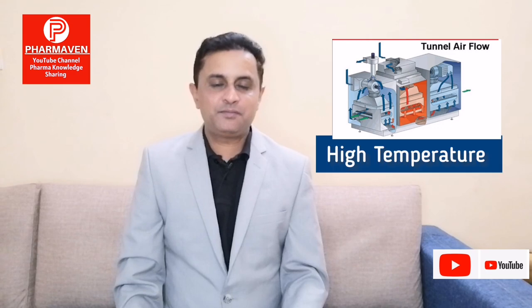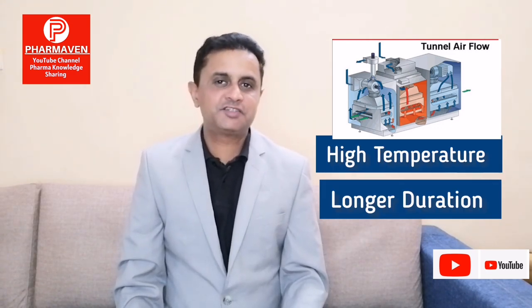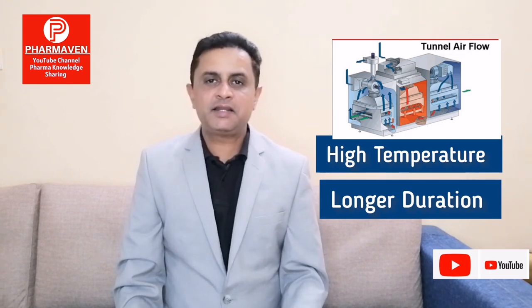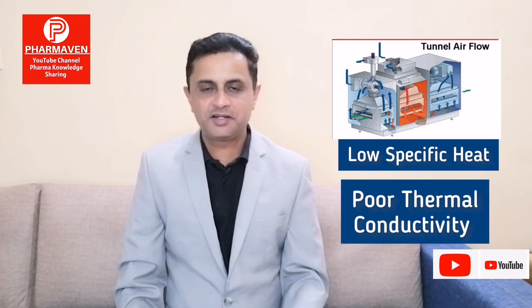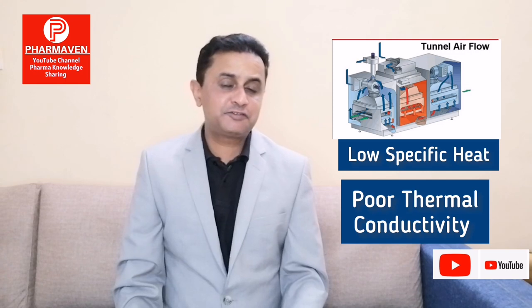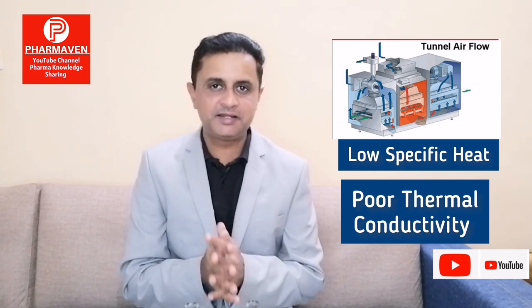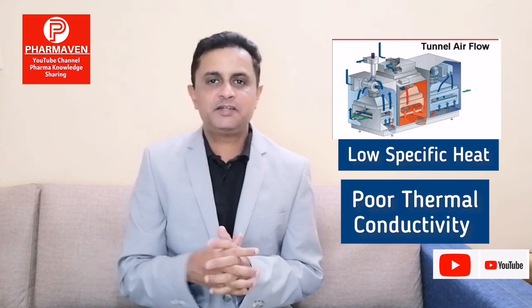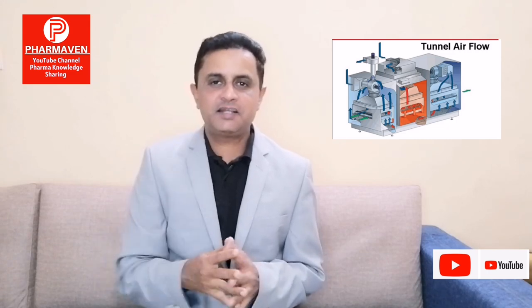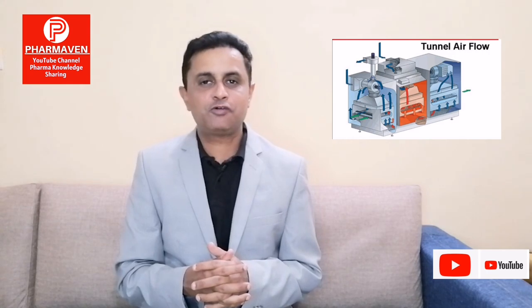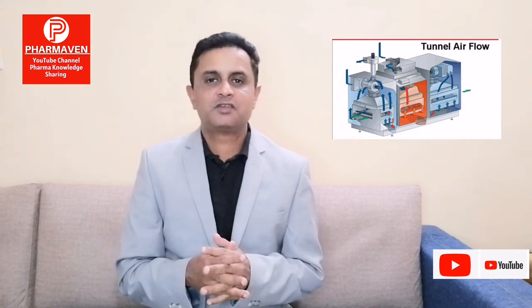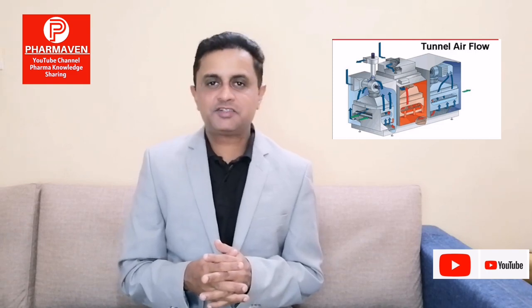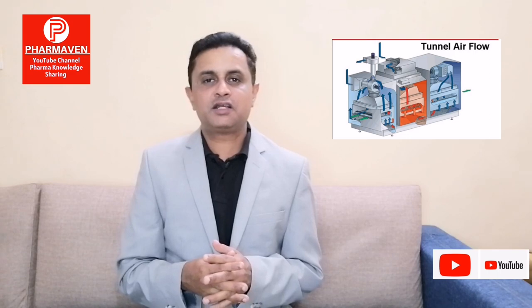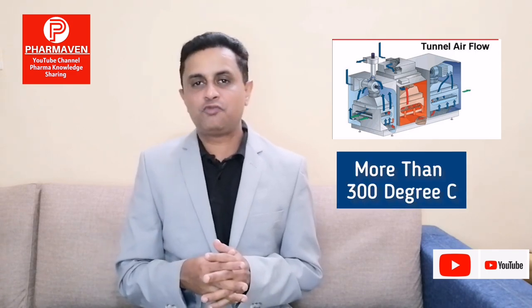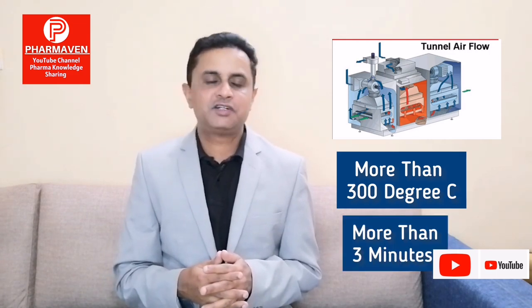So hot air requires very high temperature and longer duration for achieving sterilization. Why? Hot air has a very low heat carrying capacity compared to moist heat or saturated steam. Because hot air has very low specific heat, it carries very little heat when heated and transfers the heat in very small amounts. So it requires higher temperature and longer duration when we are talking about hot air sterilization. In batch sterilizers operating at 250 degrees, it sometimes requires 2 or 3 hours of exposure to achieve sterilization. In depyrogenation tunnels, we go for temperatures of more than 300 degrees, and it requires around more than 3 minutes inside the tunnel to achieve depyrogenation.